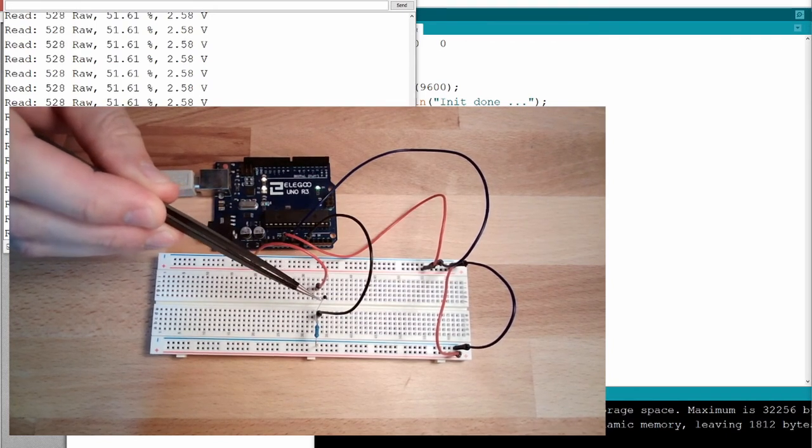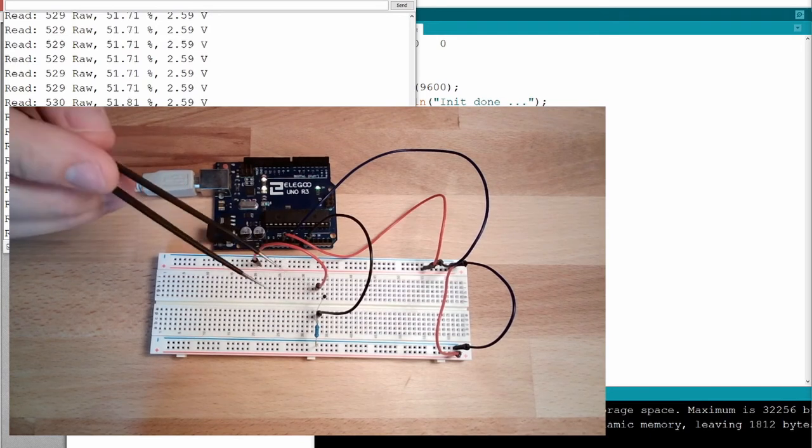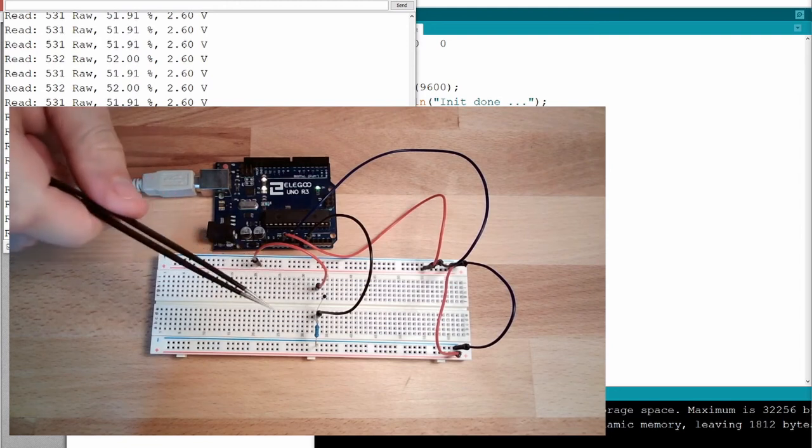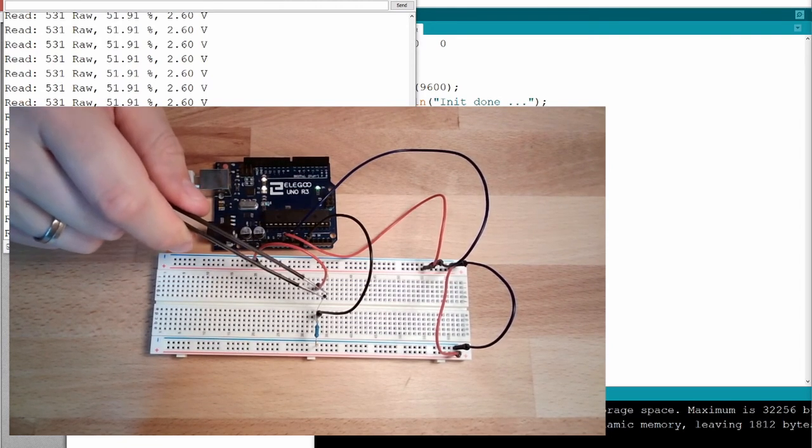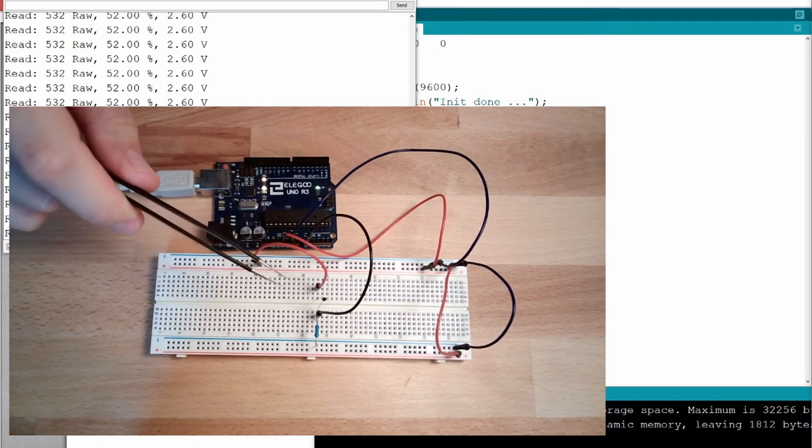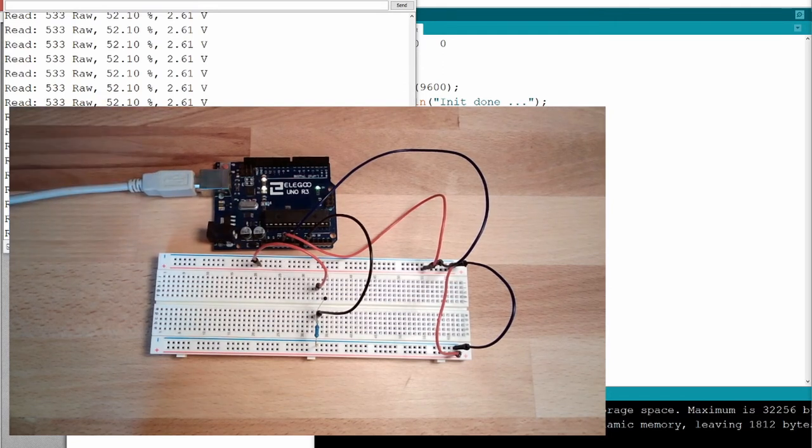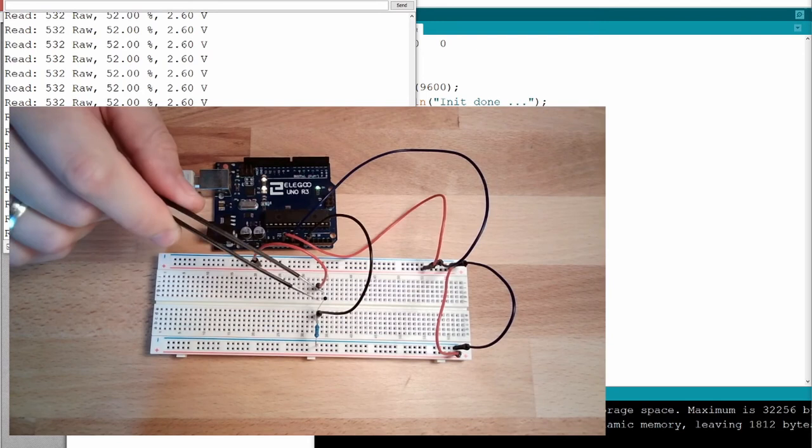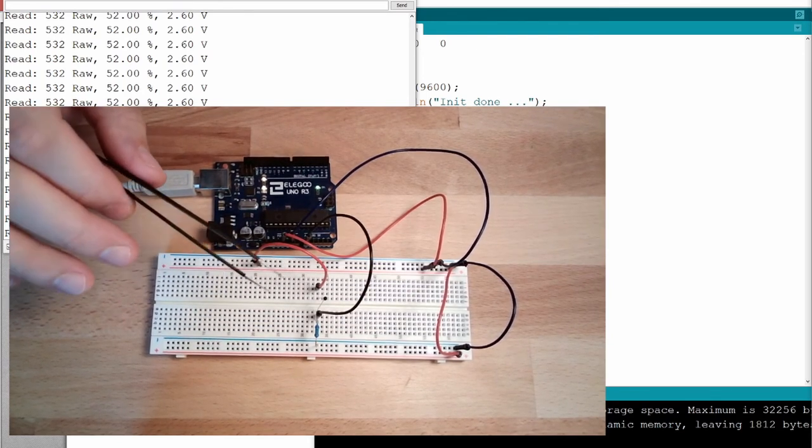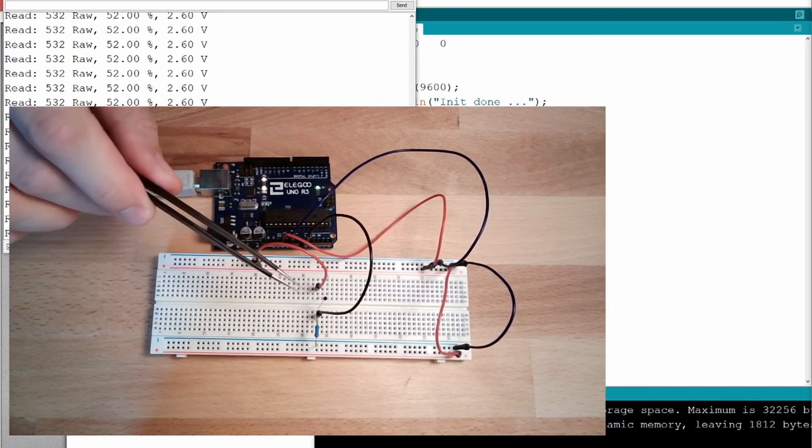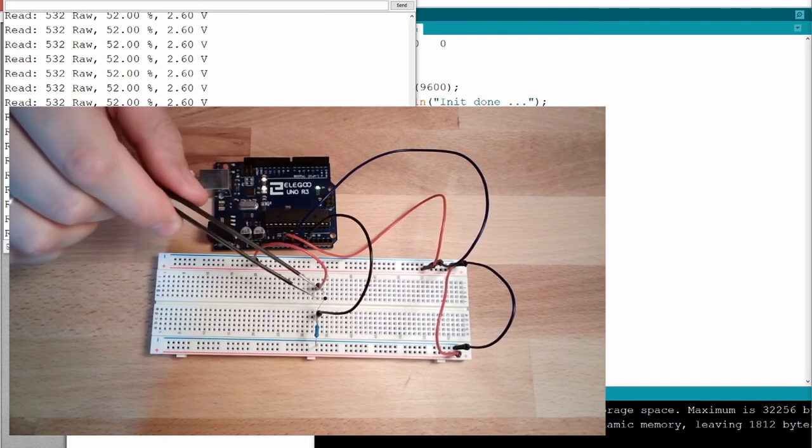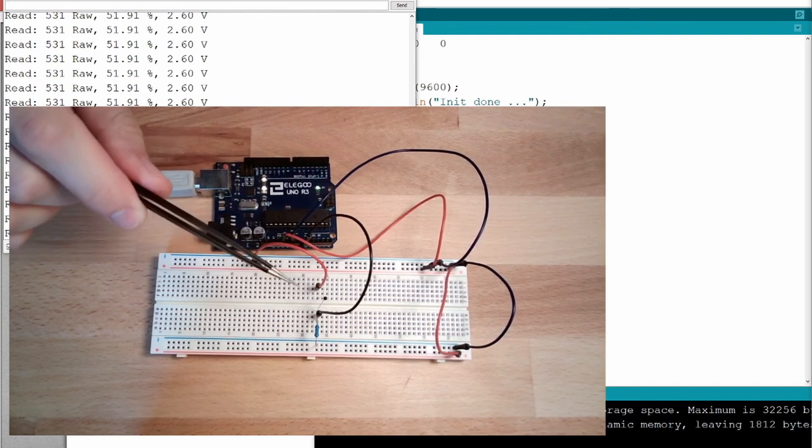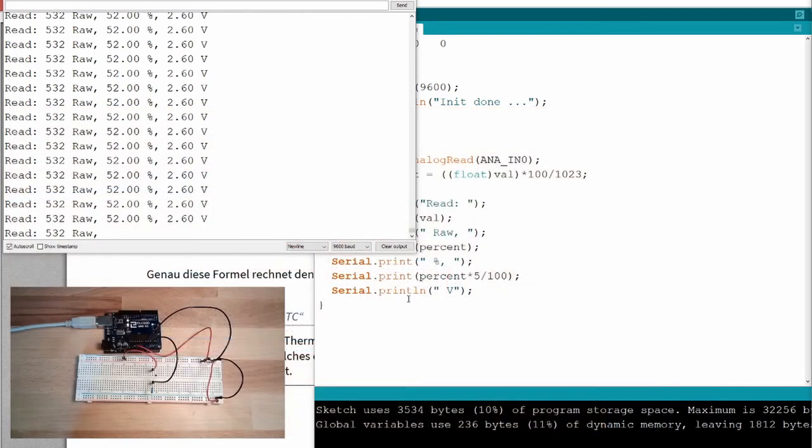But why aren't we using those type of things always? Why are we not using a chip? A very common thing is this platinum. Platinum makes less sensitivity than the semiconductor materials, and there is even a material which changes in the other way. The big disadvantage of the semiconductor materials is their non-linearity. It makes a difference if we measure around freezing or if we measure around boiling temperature of water. We then have totally different sensitivity there. Metal is much better. We can use metal in a broader range of temperature areas and the sensitivity is always constant.